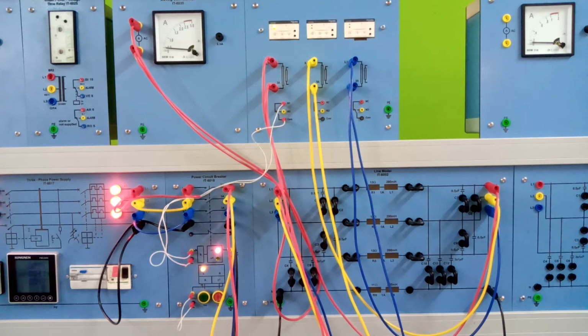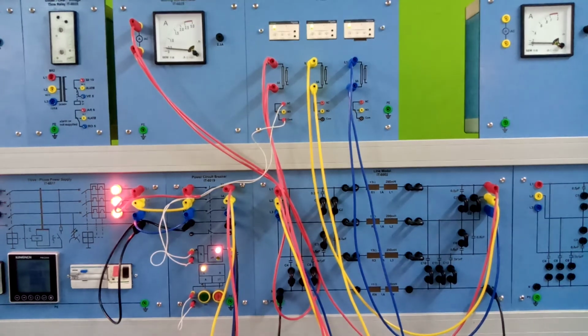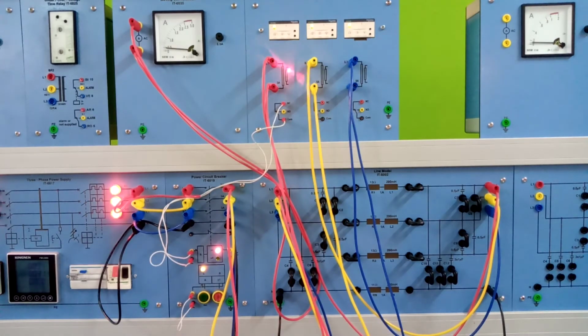Now these two are initializing. Okay, so again we just have to simulate the fault on a single phase. The first phase is the red phase, and we will simply increase load on this one. You see now it's under 0.5, and when it goes over 0.5, after 10 seconds your relay is tripped. This is identical for all three phases. You see this one is tripped and these two are blinking, so it means that the supply has been cut off, and this one is in the trip condition. So it means that the fault was in this phase.